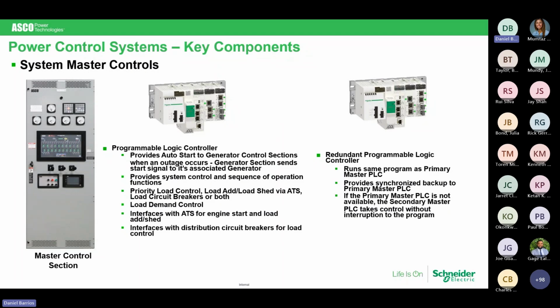You notice now we still have the analog meters shown. Depending on your specification, do you just want those now in that digital screen where you can scroll through it? The two annunciation panels that you see above the meters in the upper right hand corner, I like pointing these out because when your electrical contractor doing the installation says, how many wires do I need to pull?